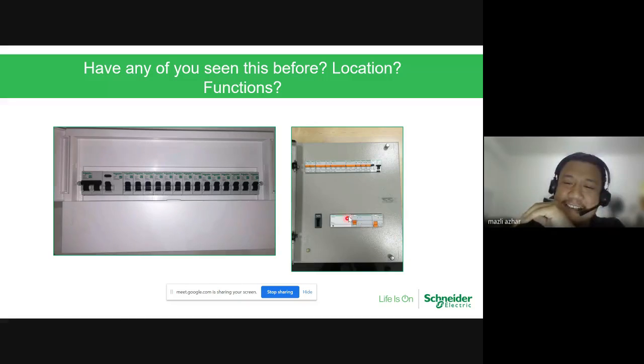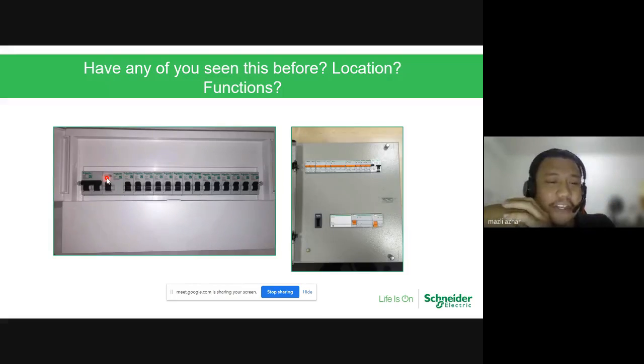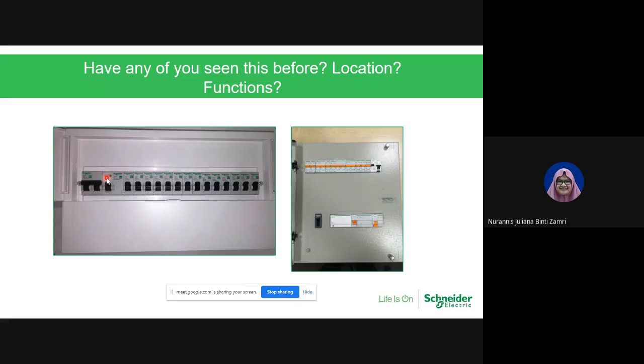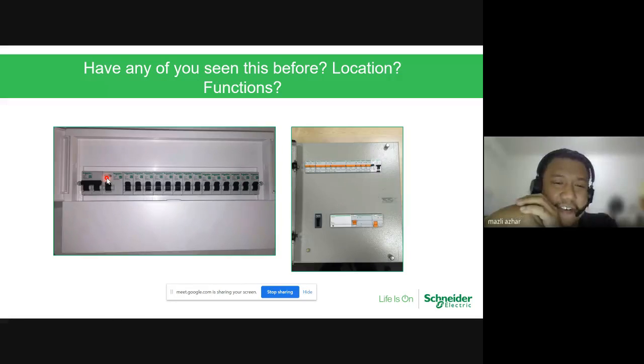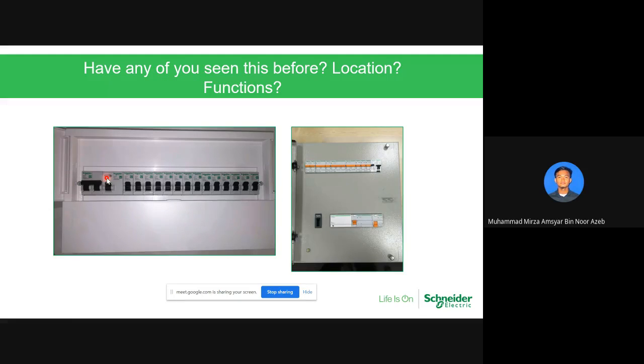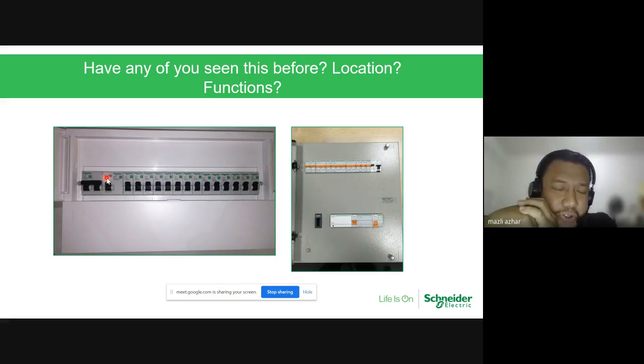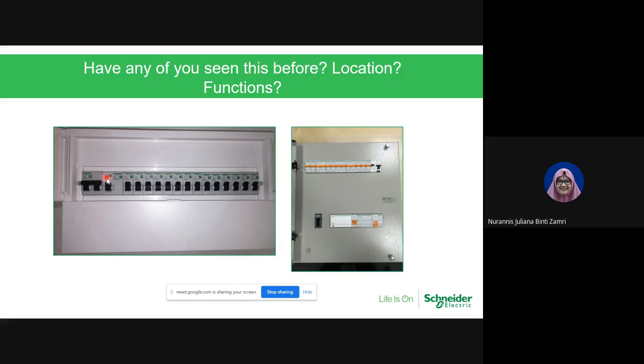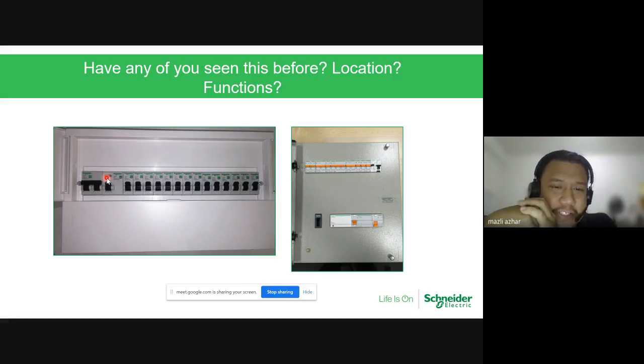And I mentioned that this thing has a white here or a black color here with the T button. So when there's no tripping, did you guys even open and test it to ensure it still functions? Yes, I push monthly. Wow. Based on the standards requirement, you need to test it quarterly or two times per year to ensure it still functions.